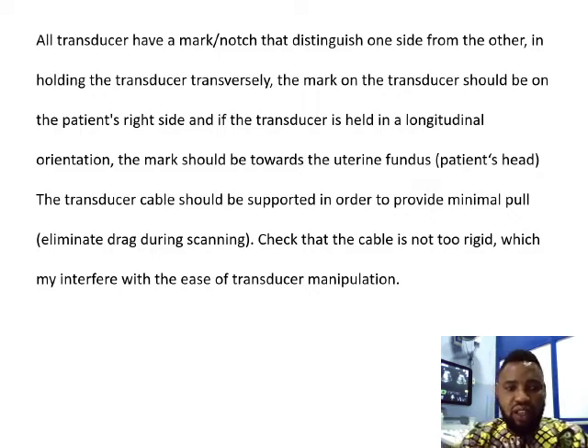The transducer cable should be supported in order to provide minimal pull, eliminating dragging during scanning. Check that the cable is not too rigid, which might interfere with the ease of transducer manipulation. So when you are scanning, the cable must be long enough and will not be pulling up and down.